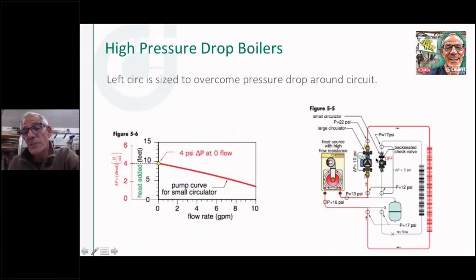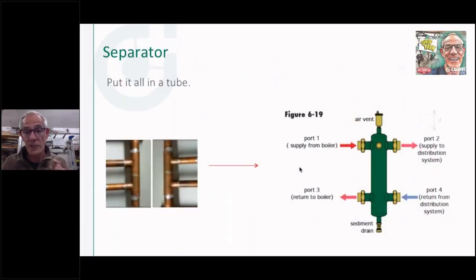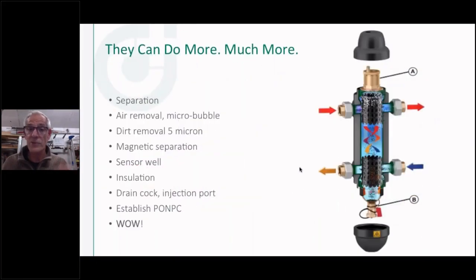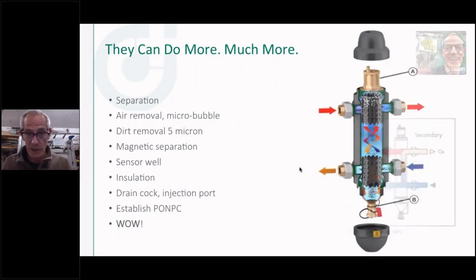So see what happens when this is a high head circulator, and you see what happens here. If I'm starting with, let's say, a 12-pound static fill pressure, as soon as I kick on that circulator, we show it right here, that circulator is developing 10-pound pressure differential. So immediately I've got 22 pounds of pressure on the discharge side of that circulator. Now this drawing is showing you something different, not pumping into the boiler, but that's why we want that delta P that pump establishes. We want that to show up in our heat exchanger as a positive pressure to make sure that we don't drop down to where we lock out because of a low pressure condition in that boiler.